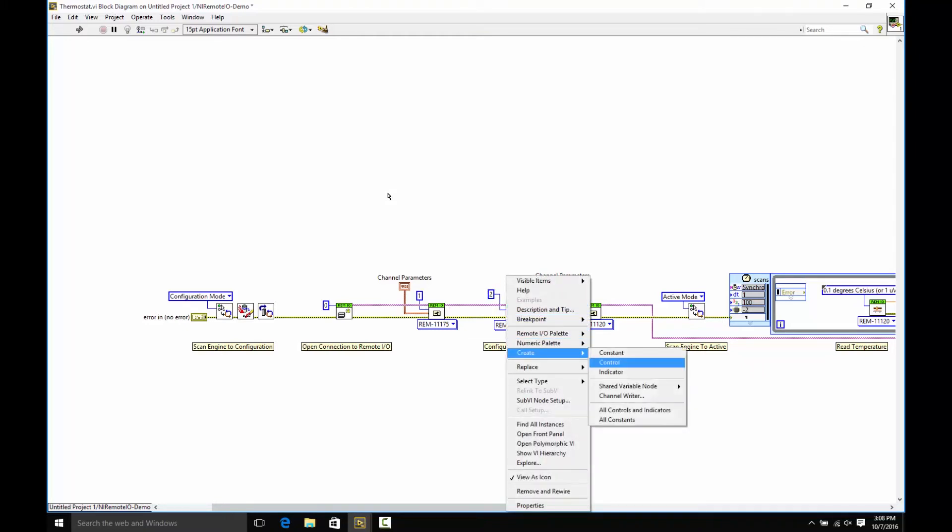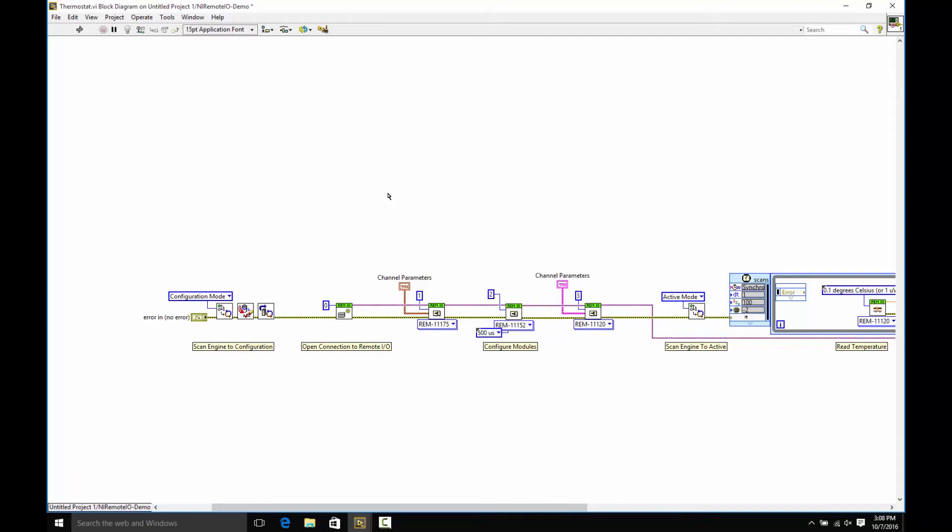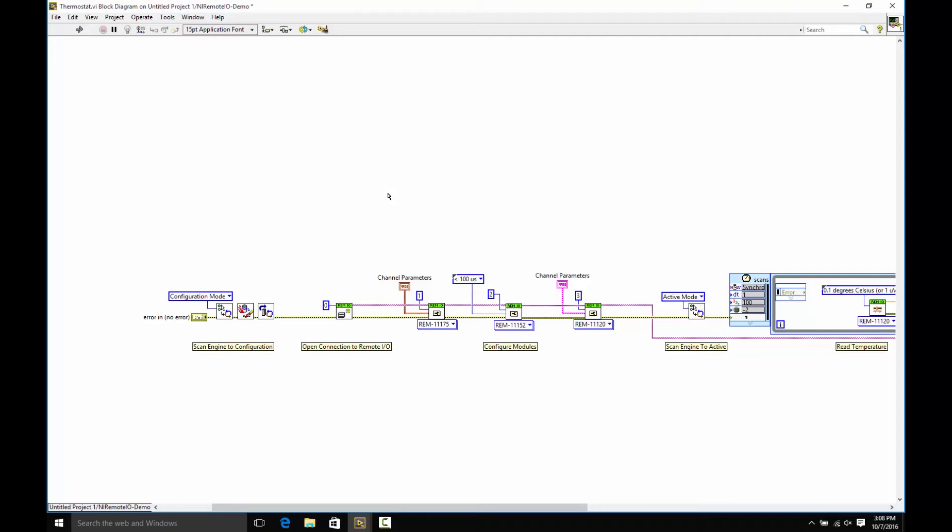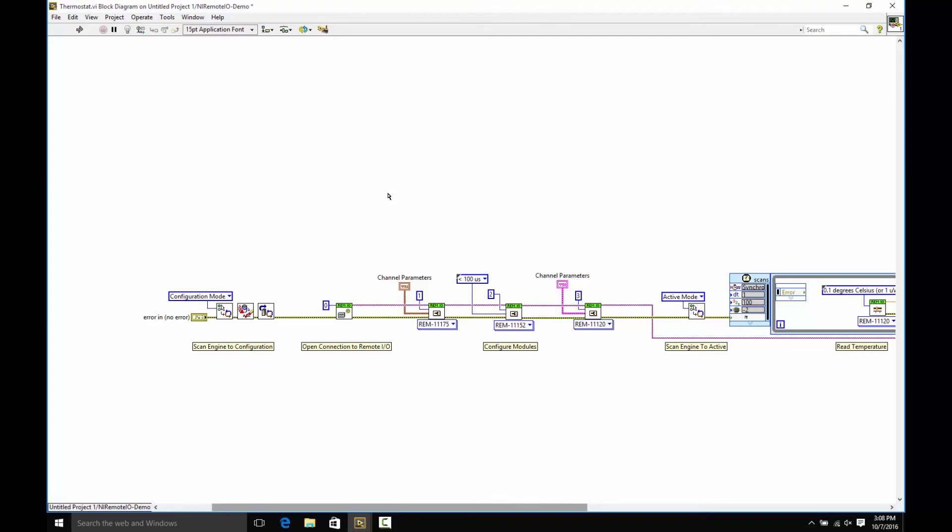Put that there. I'm going to create another constant for the one configuration item that we have for this digital input, and that's a filter time. This will allow you to debounce your digital inputs or otherwise filter out noise. We're going to use the fastest setting, less than 100 microseconds.